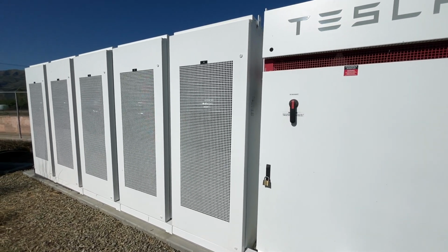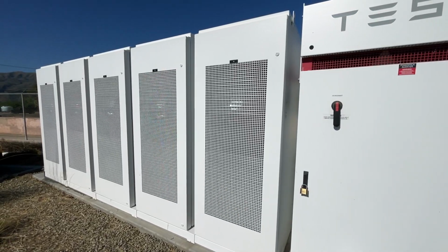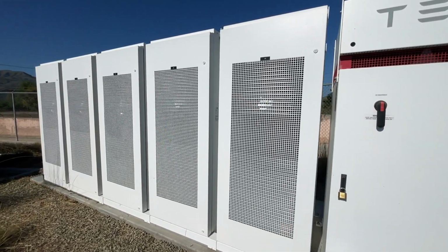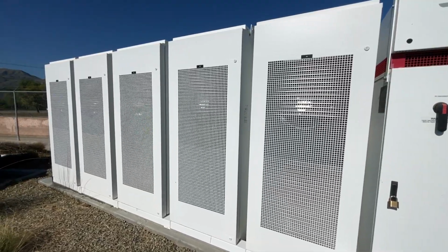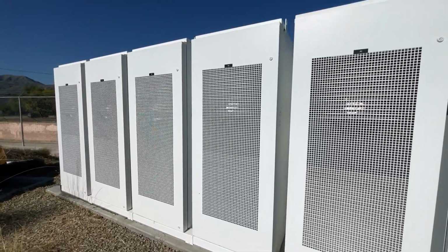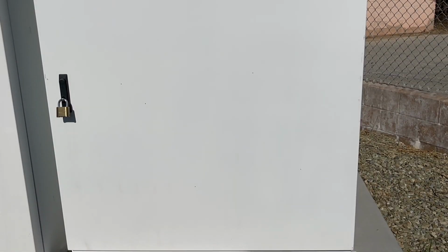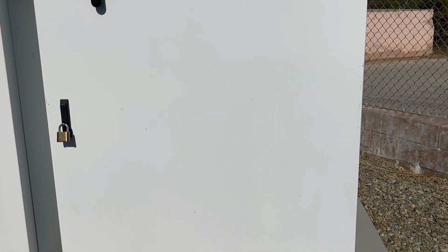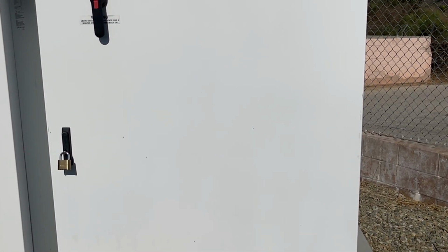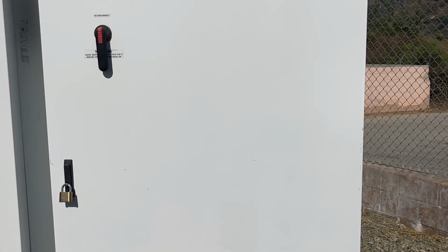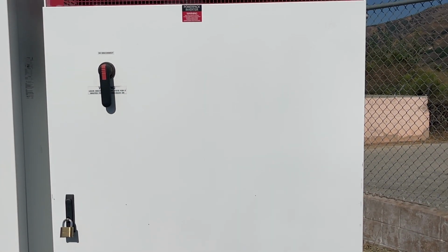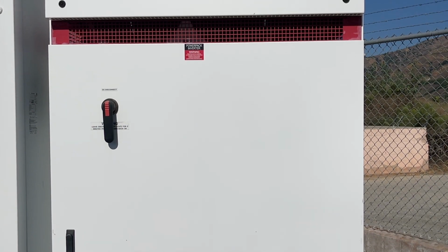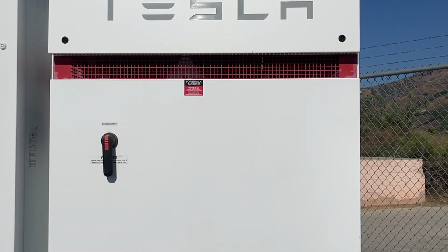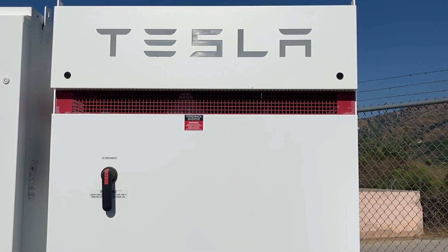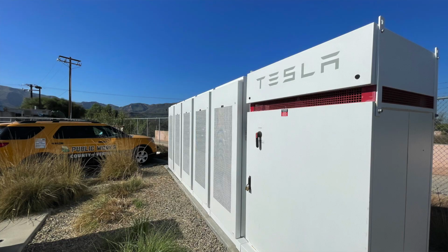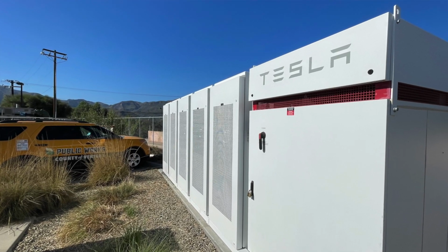The container closest to me is the inverter. It converts power from AC, which we get from Edison, to DC, which is how batteries like to store their power. We can store power coming in, and when we want to take power back out, this converts it back from DC to AC, goes through the microgrid controller, which decides whether it's feeding the plant or feeding Edison. It comes with all sorts of safety features to make sure there are no hiccups along the way.